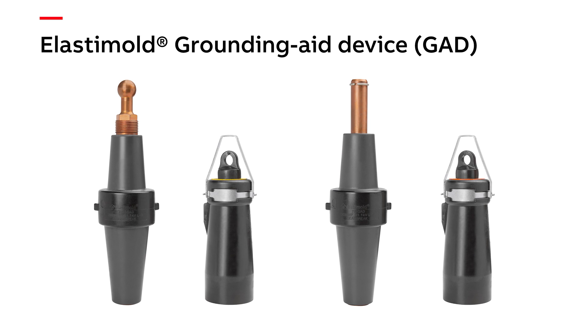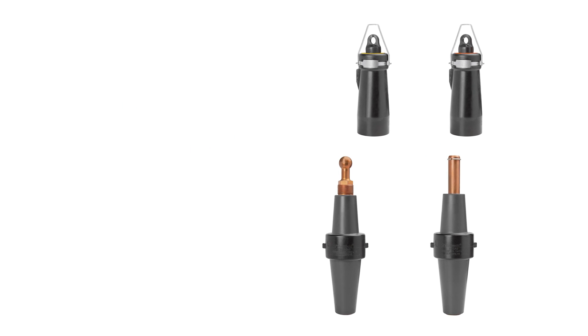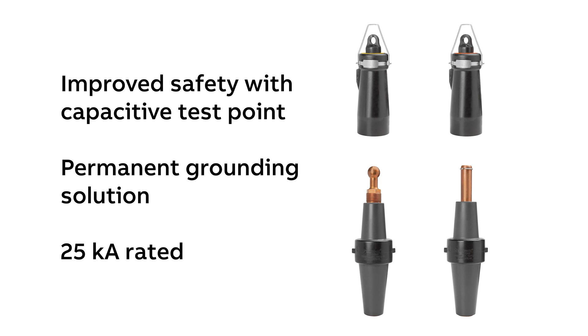The last product I want to share with you is our GAD. It's a 600-amp rated grounding-aid device with a 25kA fault current withstand. It gives you a permanent grounding solution for your 600-amp system, rather than having to use a 200-amp grounding elbow with a 10kA withstand.